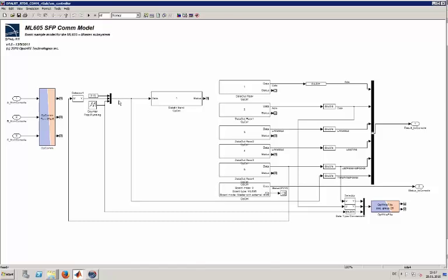The third value I will receive from RTDS is the time step counter on their side. So we do a loopback on our side here. We send back their counter to compute the round trip delay of the communication on both directions. And they do the same thing for the fourth value.